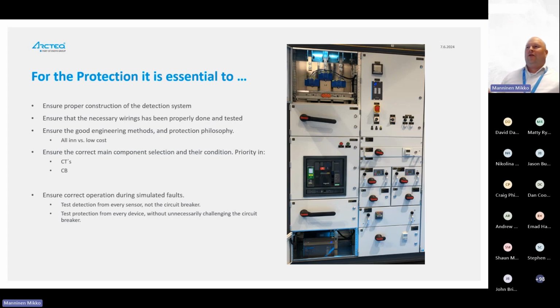You need to ensure that good engineering methods have been used, protection philosophies. Is it built like a very low cost system, or is it built all in with the best available technologies? Ensure the correct main components selection and the condition, priority in CTs, VTs, circuit breakers. And simulate the faults. Test detection from every sensor. That is essential. Test detection from every sensor, but do not test the circuit breaker from every sensor.